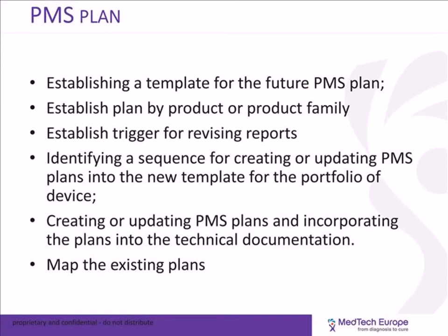Identifying a sequence of creating a PMS plan: a new template for the portfolio, creating or updating the PMS plan, and incorporating the plan into the technical document. No matter what class of product you have, the technical documents now need to include this PMS plan, and map with the existing plan, realizing that we're not starting from scratch here. We do most of what is required, but we need to create the feeds so that the PMS plan can be updated on a regular basis.